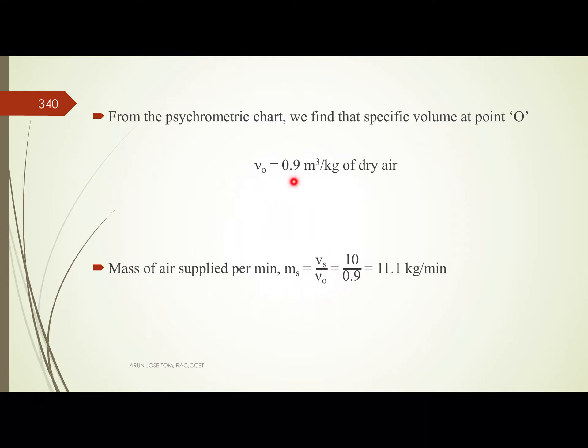The specific volume at point O is 0.9 cubic meters per kilogram of dry air. The mass flow rate of supply air is: discharge divided by specific volume, which is 10 m³/min divided by 0.9, giving 11.1 kg per minute.